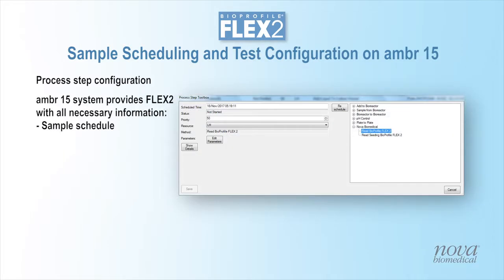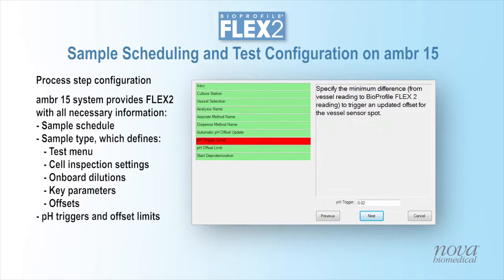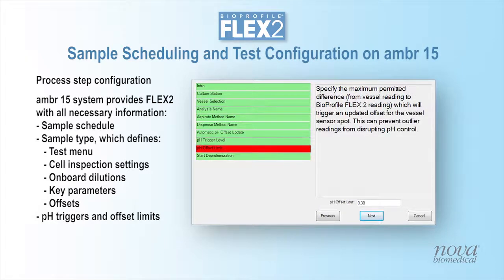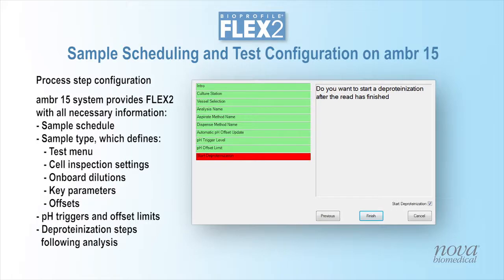Process step configuration includes sample scheduling, selection of the sample type which defines the test menu, cell inspection settings, onboard dilutions, key parameters and parameter offsets, as well as pH trigger points and offset limits, and deproteinization steps following analysis.